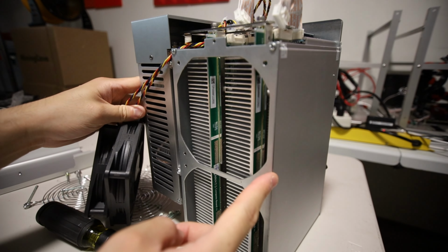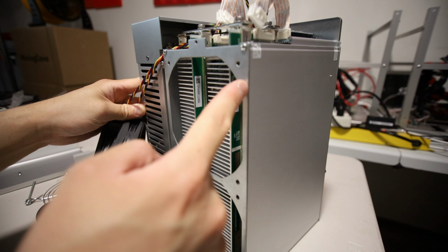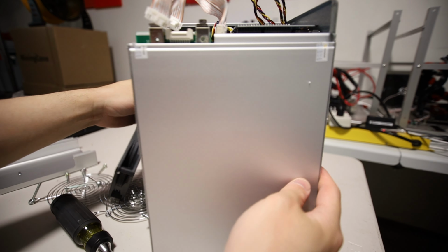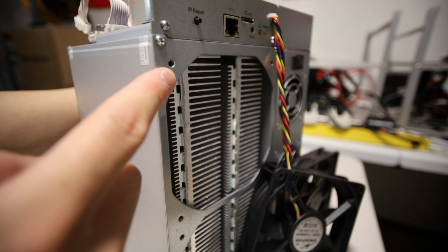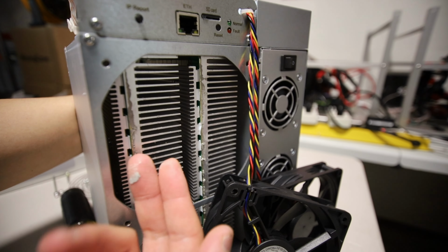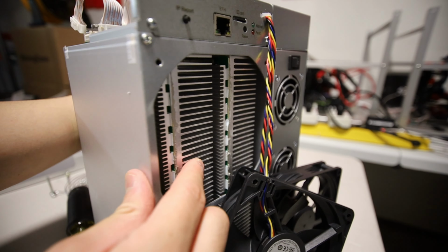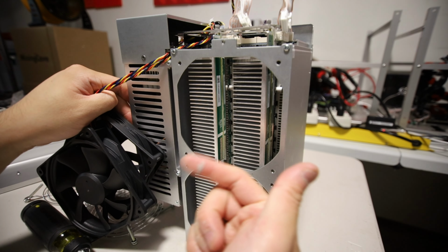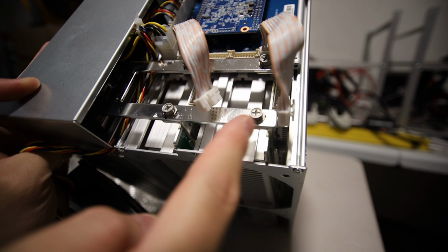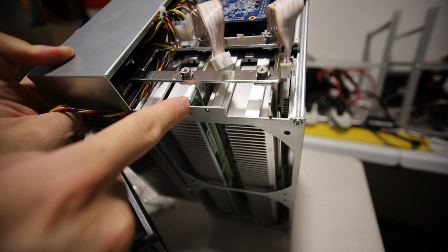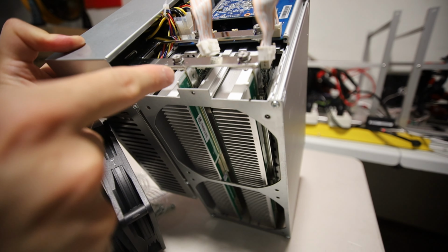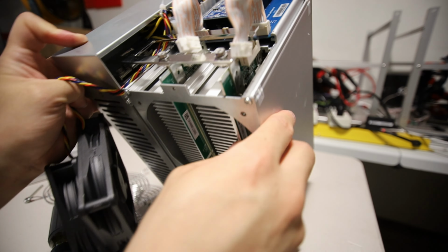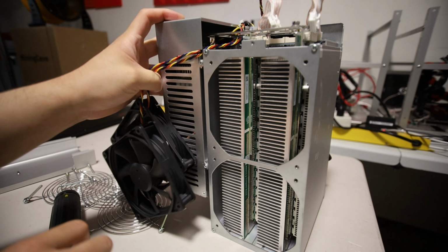Let's go ahead. I can take off this back one. Can I take off the front side? One thing I'm curious about: will these slide out the front way or will these slide out the rear? I'm gonna go with sliding out back this way. And it looks like I do have to unscrew, see these bus bars for the power going in, it's bolted into the ASIC boards here. Okay, so let's do that as well.